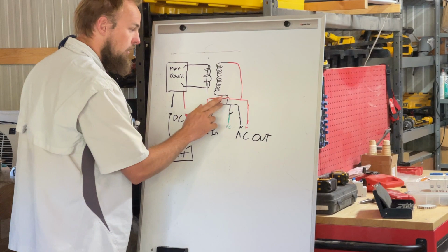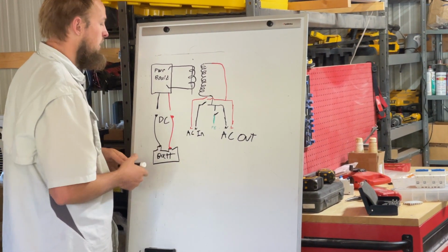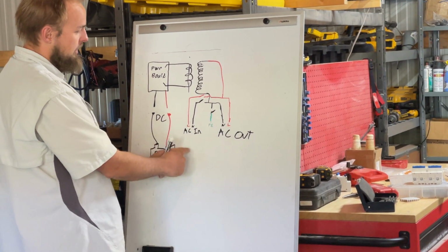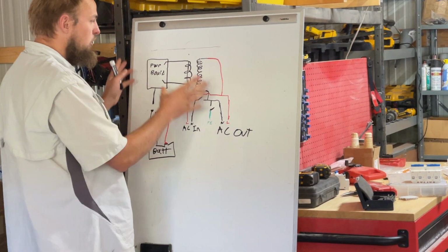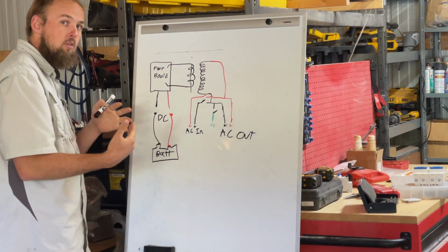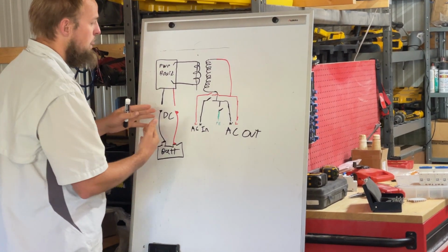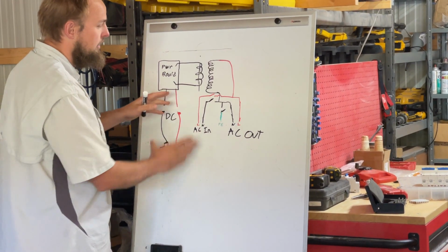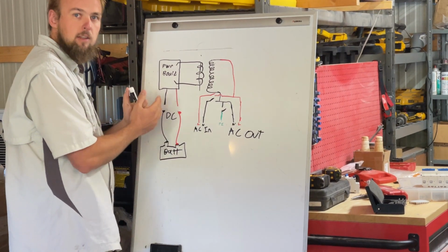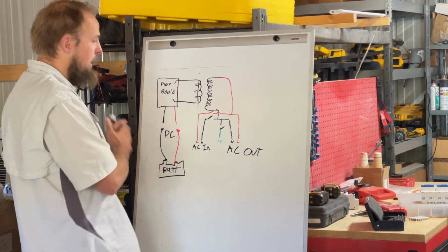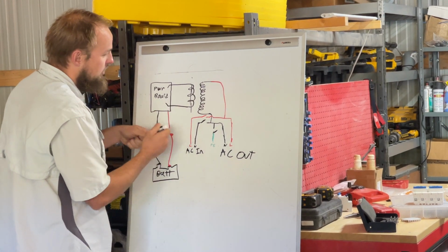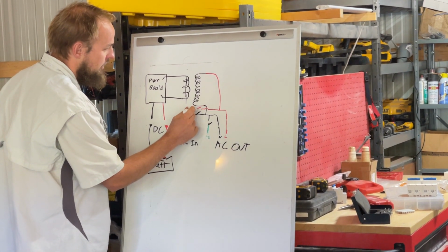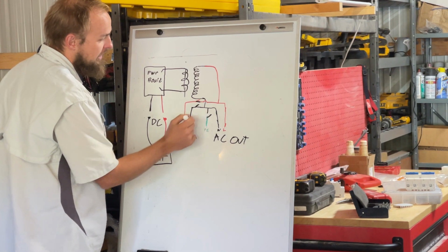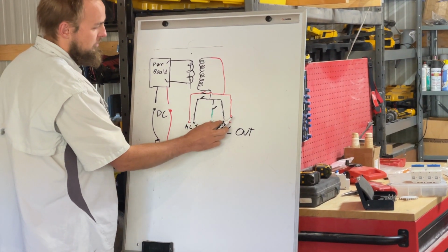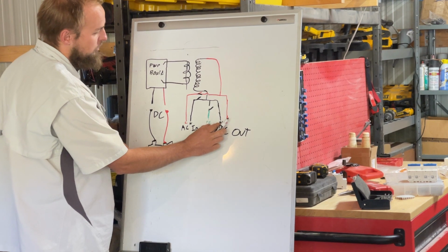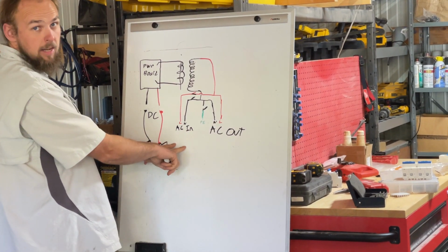And we have tested that on this inverter, and that's working fine. Now, also, if you put AC input to here, then the inverter is going to assume that whatever source you're tying into this inverter, like a generator, is already connecting neutral and ground upstream in that source. And so when these contacts close to connect that power source, this contact opens. So this is not producing a path between neutral and ground anymore. It's assumed that that's going to happen upstream.